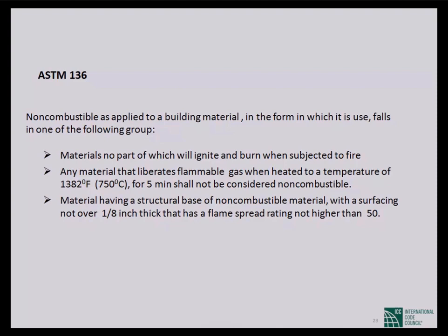I repeat again, a material which has a base structural element which is non-combustible, but if it is coated with something, if it is less than 1/8 inch thick, and if it gives some vapor, and that is not flammable, then you say it is non-combustible. If it continues flame, ignites, then it will not be non-combustible, it will be combustible. So you have 3 different things. One is which directly ignites, and another is which is subject to certain temperature, 750 degrees.